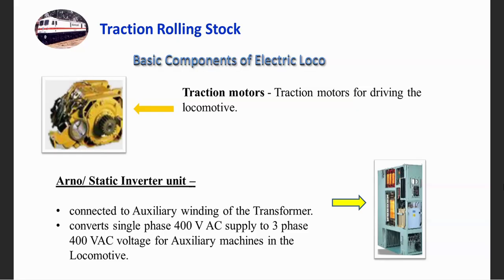As of now it is a static unit, but earlier we had a rotary machine which converted single phase to three phase power supply, and it was one of those areas which required a lot of maintenance activity. There were a lot of failures in the Arno converter, and even unbalance in the mounting arrangement used to result in a failure.